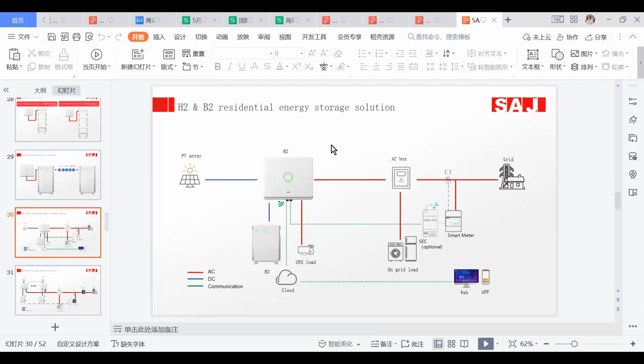Here we have 3 working modes. The first is self-consumption mode. That means the energy generated from the PV panels first feeds the on-grid load and then charges the batteries. If there is more energy, the surplus energy will be exported to the grid. And when there is no PV power, or the PV power is very small, firstly we use the energy stored in the battery to feed the on-grid load. We could set the discharging power. This method is to minimize the interaction with the grid.